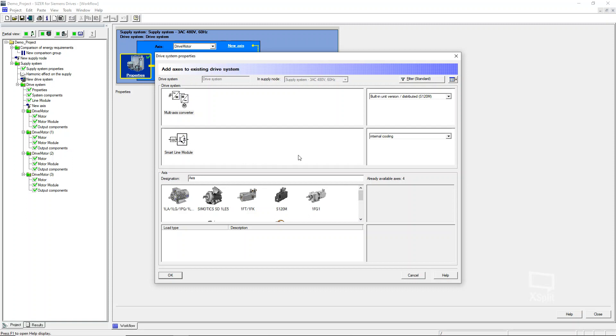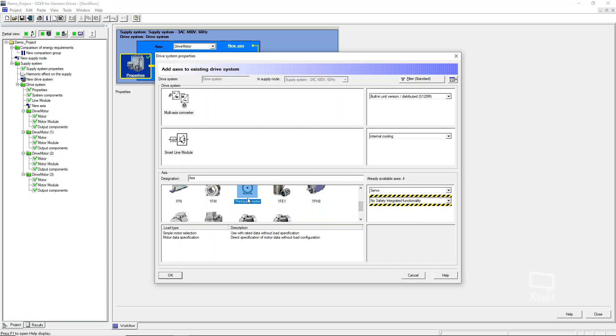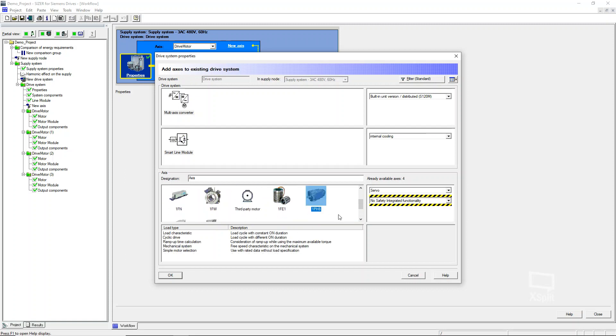The active line module, because it has that boosting capability, gives a higher DC link voltage. Normally what these motors are going to be seeing is a smart or basic line module, so it's going to be around that 620, 640 volt DC link, depending on what your input voltage is. Previously we did third party motors. Well, today I want to go through and specify a 1PH8 motor.